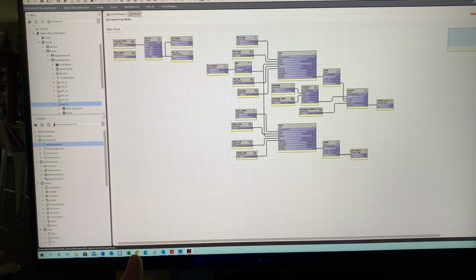So we've had some applications where it was an old church, and the church was a couple hundred years old, and they had this $5 million organ that was inside the church, and it had to be a specific humidity or the organ would get out of tune. So the MEP wrote this sequence where the chill water valve would go to 100%, and then what we would do is we would take this VFD signal, and no matter what, the air handler would run at 60 hertz.